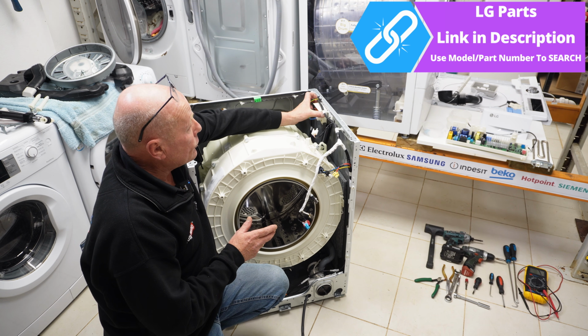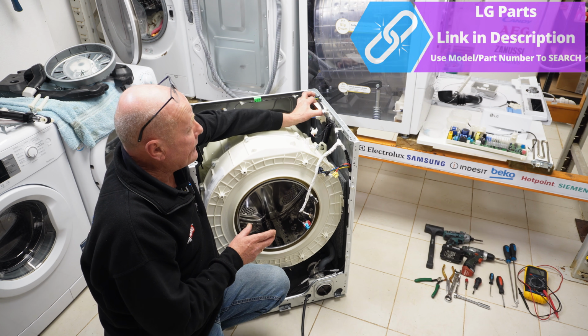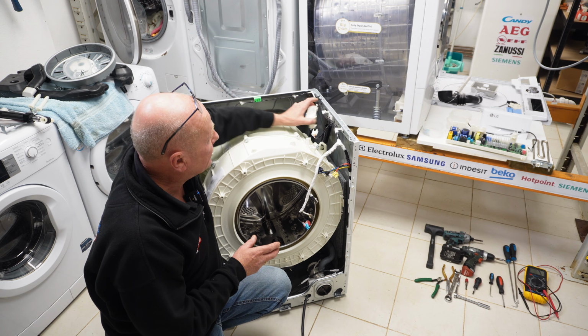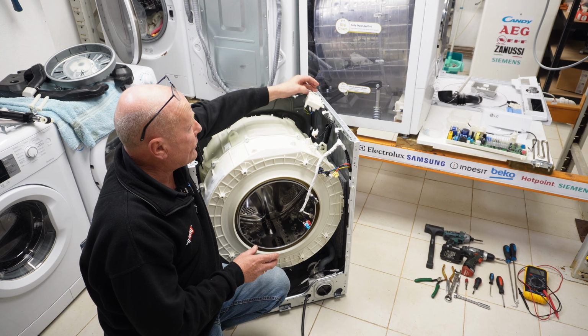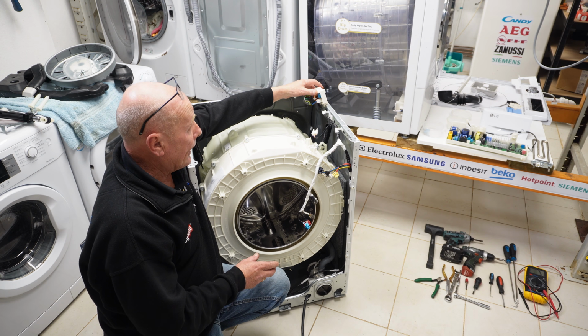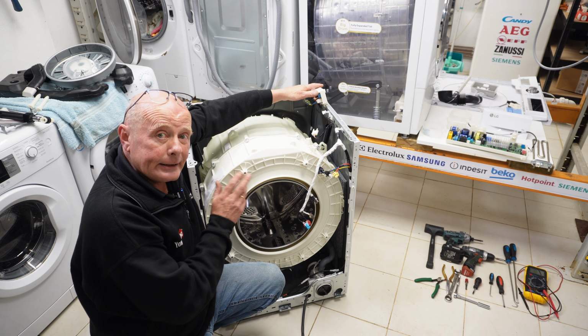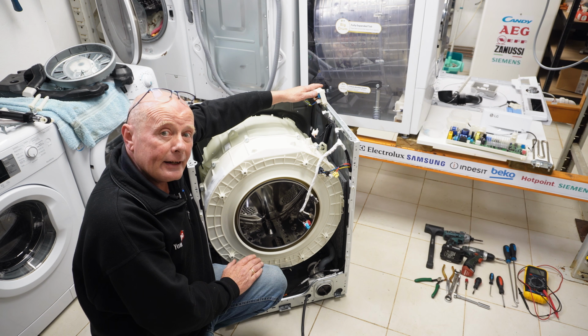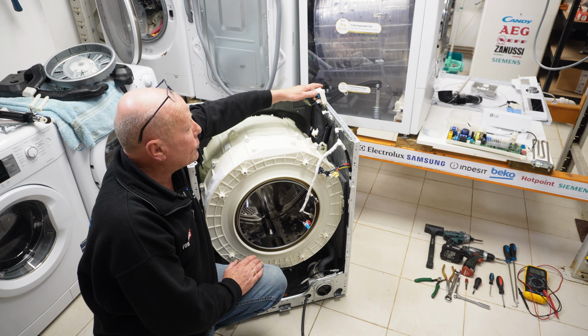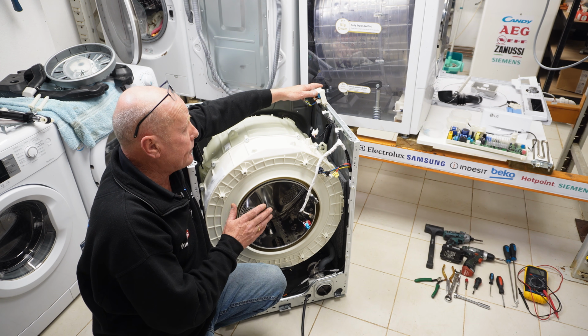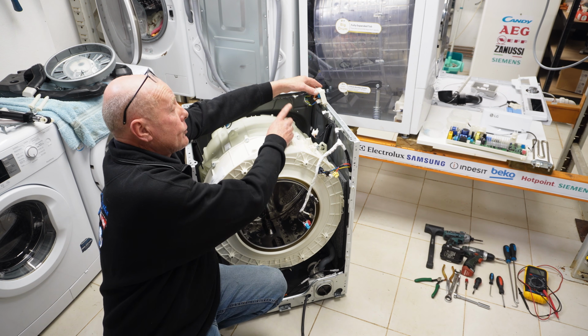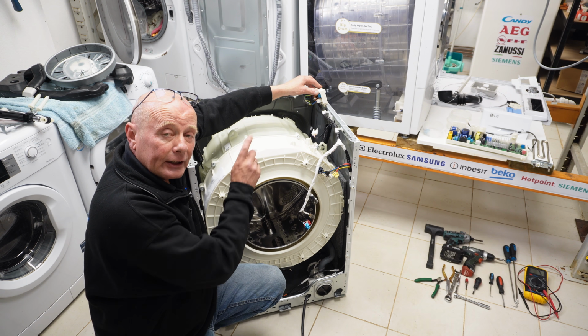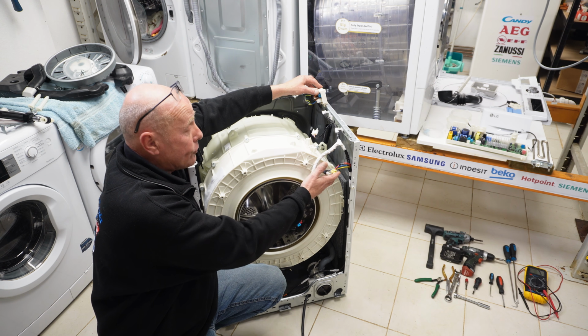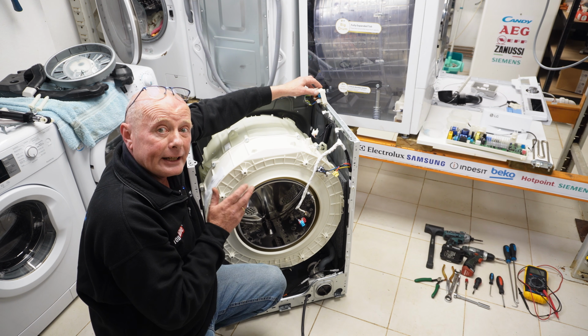Basically, this is straightforward to come off. There's a clip at the back. You just press that clip up, and then this will slide out. And there we have the suppressor or filter, electrical filter. PF could be related to this. That is an error where it's a power failure. Normally it just means that the power's gone off on the property when you have a PF error, but if the suppressor was open circuit and not passing electricity through to the circuit board connections, then this also could relate to a PF error code.